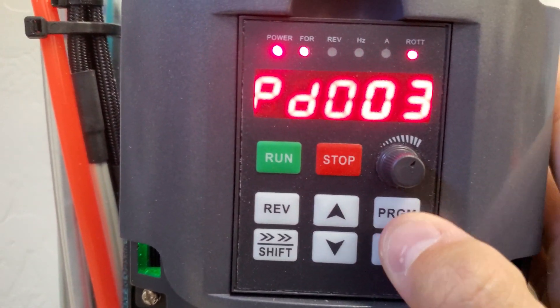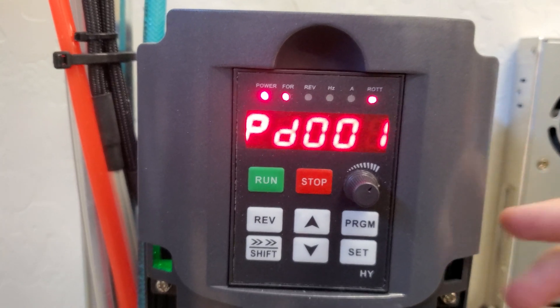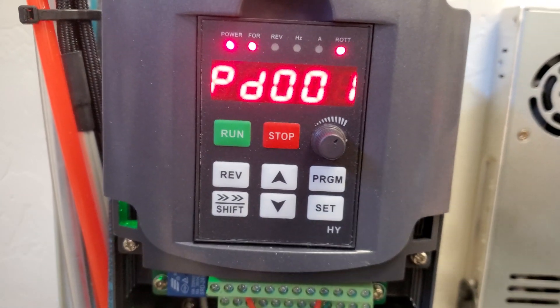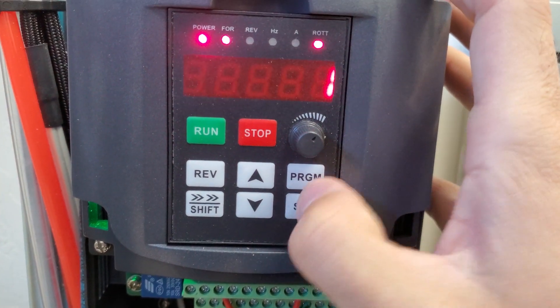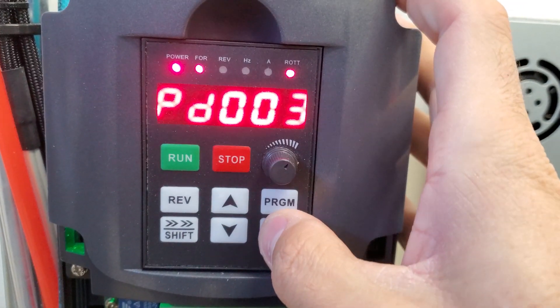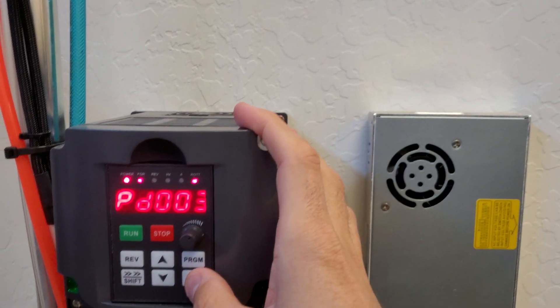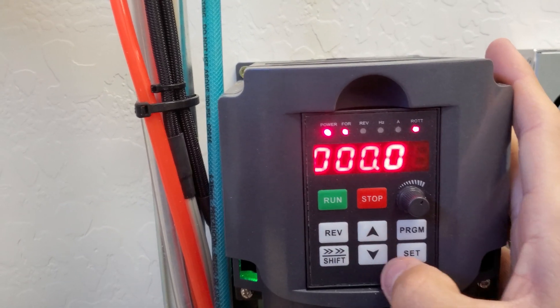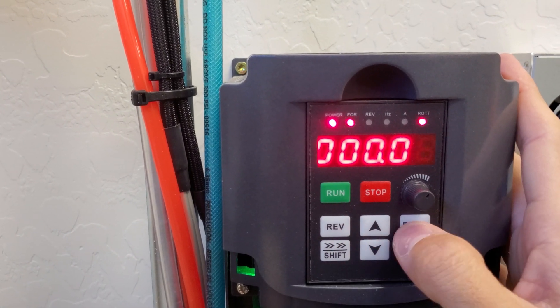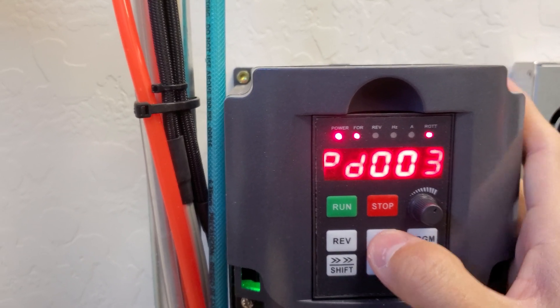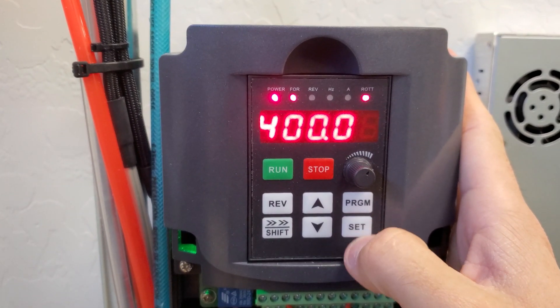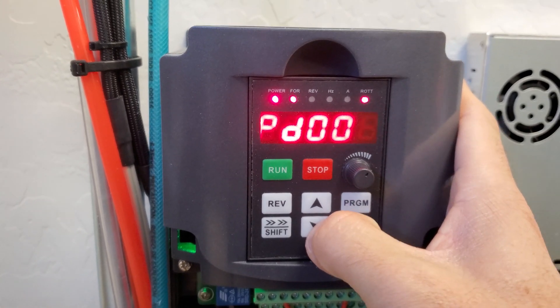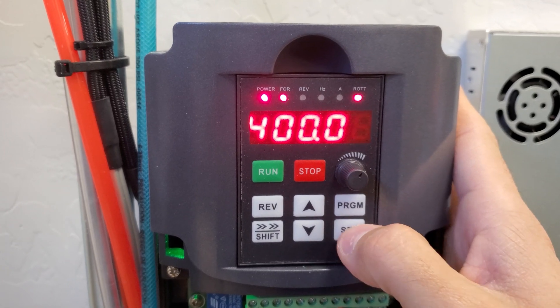So yeah, back to the programming. I'll start over. PD013, set that to 8. Resets all the settings. Go back into PD001, you're going to set that to a 1. 002, you're going to set that to a 1. And then 003, set that to 0. And then go into 005, set that to 400. Set that. And then go back down to 004, and set that to 400 also.